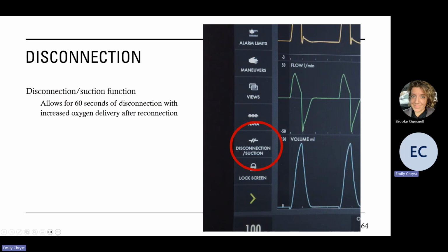And then we have our disconnection button, or disconnection/suction. So this is going to allow us 60 seconds of disconnection where it's not going to actively ventilate. So you hit this button and you disconnect your patient. It's not going to scream at you, which is nice. But additionally, it's going to have a countdown timer. So you know when 60 seconds of disconnection has passed and you can start thinking about connecting your patient again.